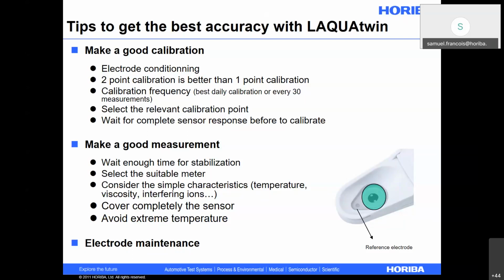It's also very critical for the LAQUAtwin to cover the sensor completely. As we can see on the little pictures here, the electrode is made with two parts. One part is here, the electrode, so it can be pH or the ion selective electrode. On the tip, we have a little point, which is the reference electrode. So when we do a measurement, we want our sample to cover these two points completely. We don't need to have a lot of sample on the sensor, but at least we want to have the sample cover completely the two parts of the electrode, so we have a good contact for the current.